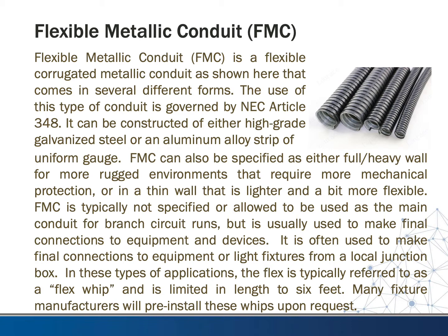Flexible metallic conduit, or FMC, is a flexible corrugated metallic conduit that comes in several different forms. Its use is governed by NEC Article 348. It can be constructed of either high-grade galvanized steel or an aluminum alloy strip of uniform gauge. FMC can be specified as either full or heavy wall for more rugged environments requiring more mechanical protection, or thin wall that is lighter and more flexible. FMC is typically not specified as the main conduit for branch circuit runs; it is usually used to make final connections to equipment, devices, or light fixtures from a local junction box. In these applications, the flex is typically called a 'flex whip' and is limited to six feet in length. Many fixture manufacturers will pre-install these whips upon request.